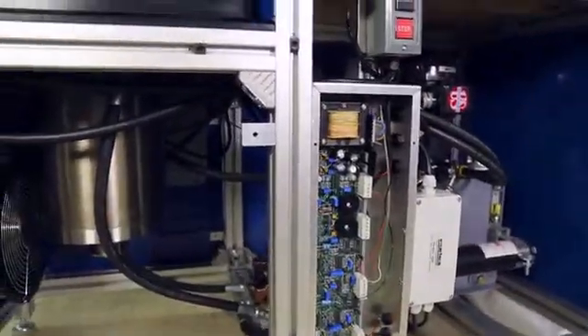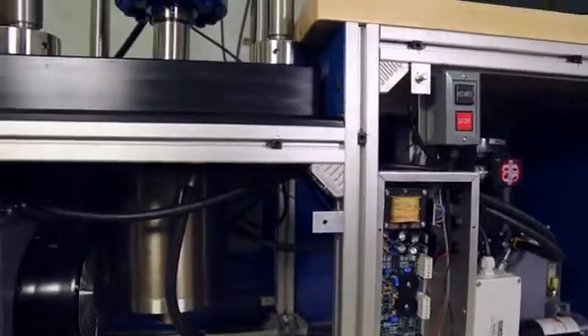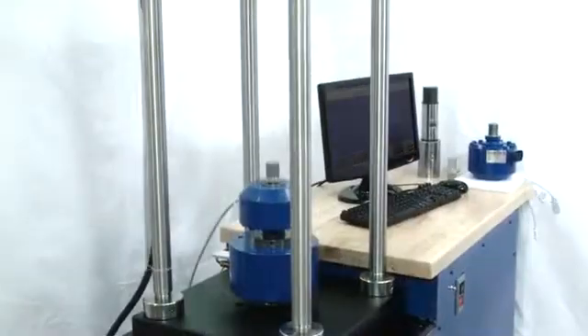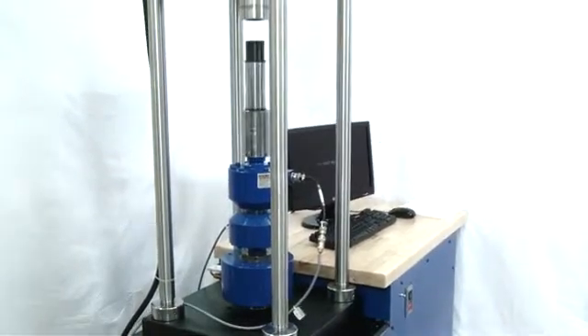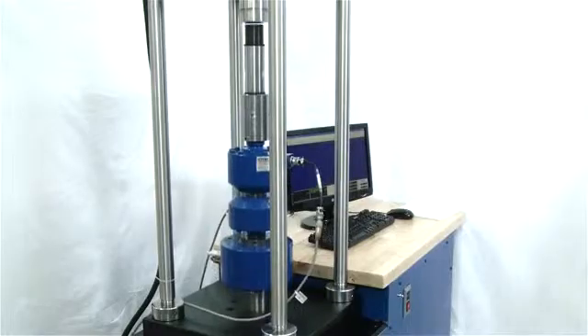The Gold Standard Calibration Load Frame provides both compression and tension calibrations in a single setup and installation of the test load cell. It takes less than five minutes to complete a calibration and automatically create the corresponding tables and graphs.